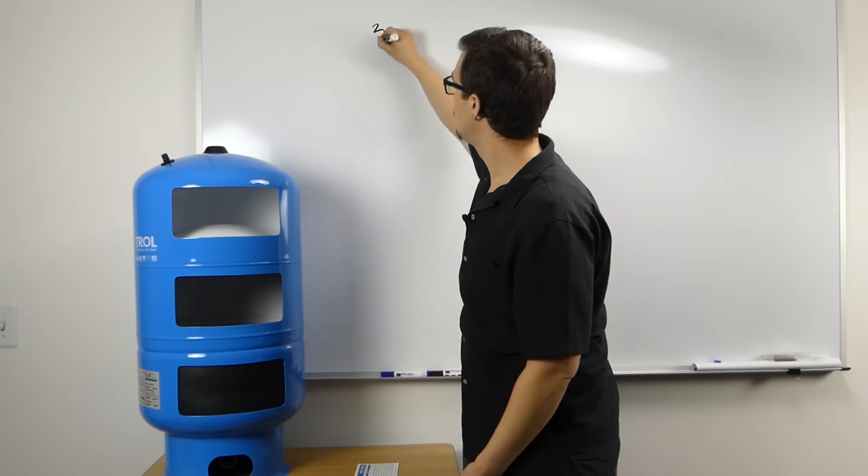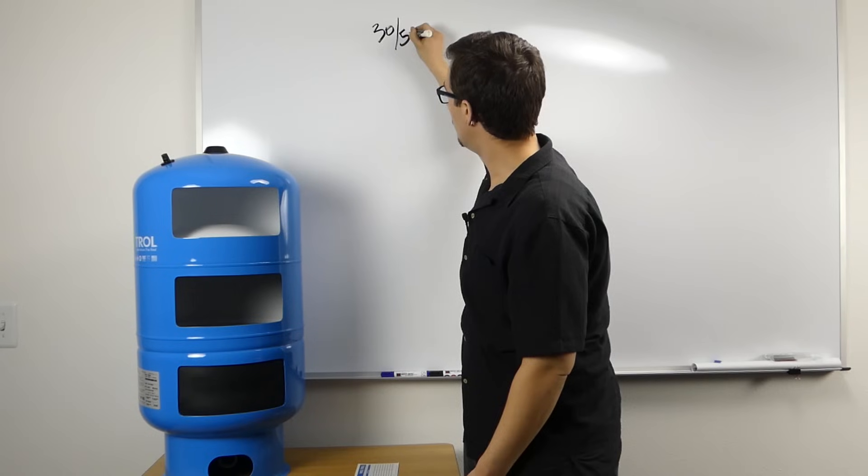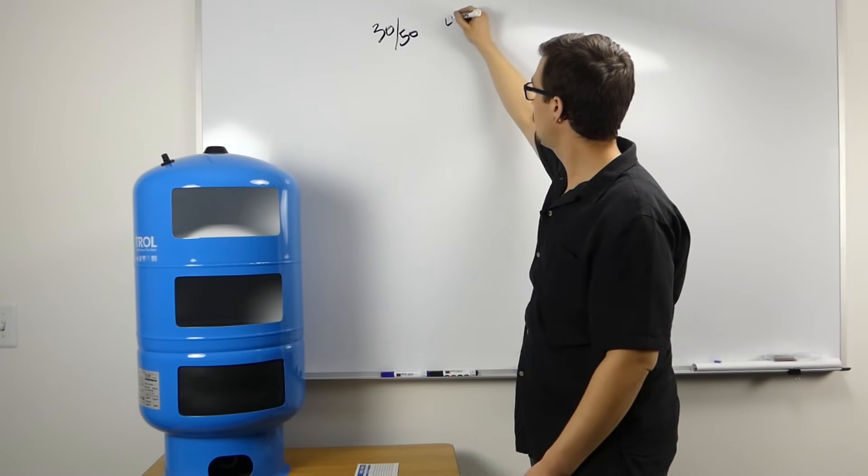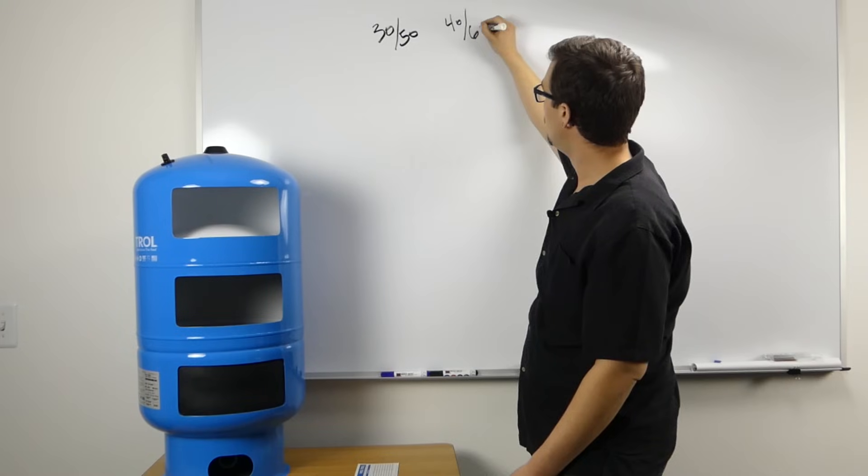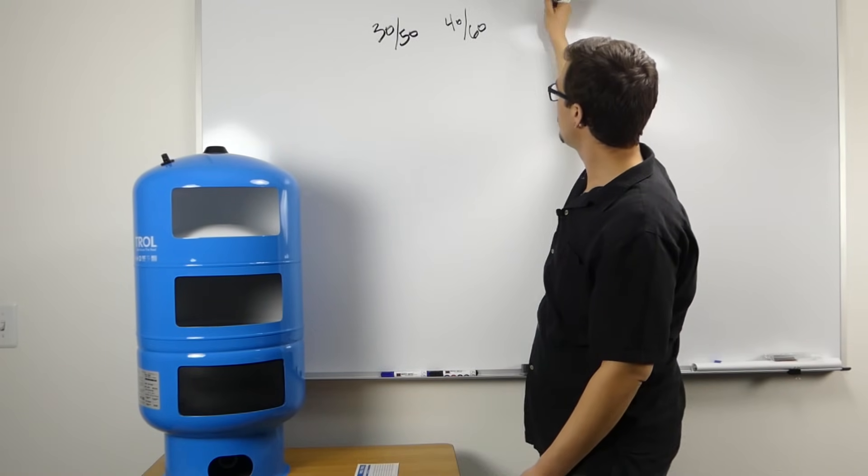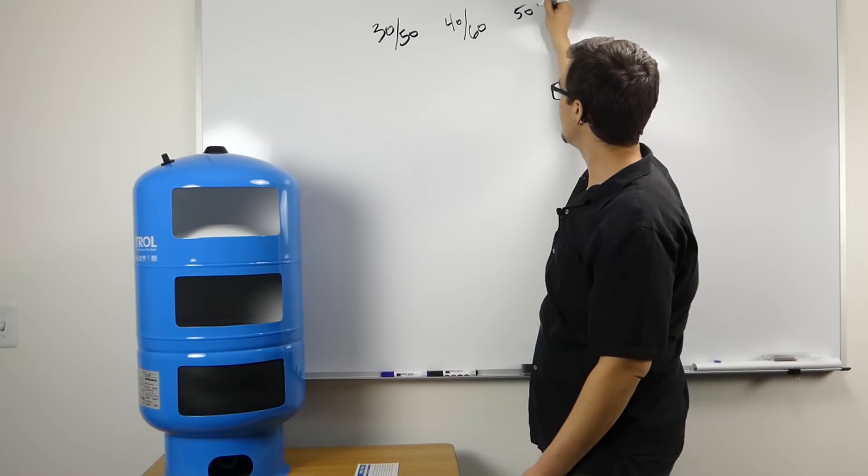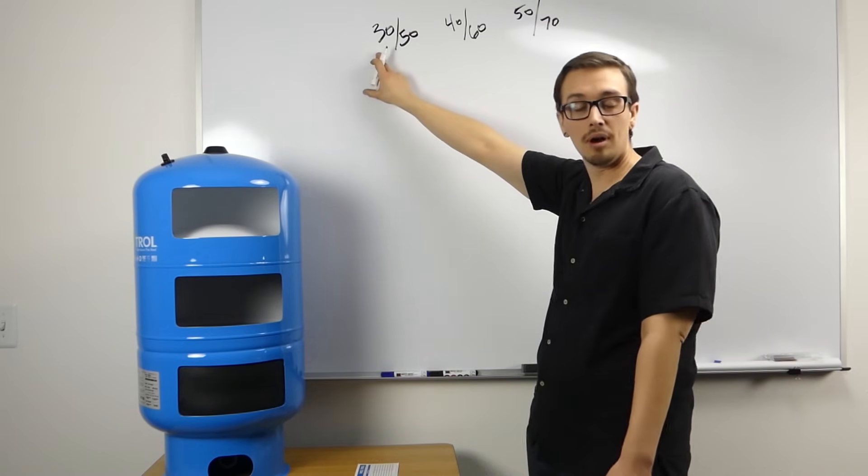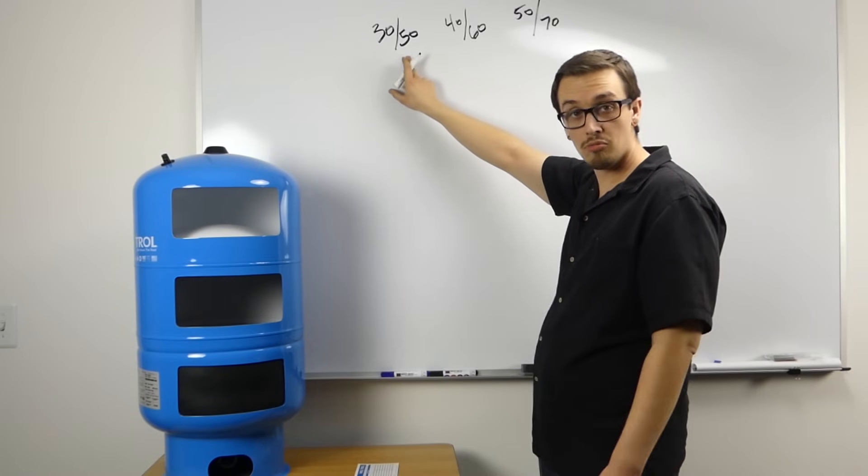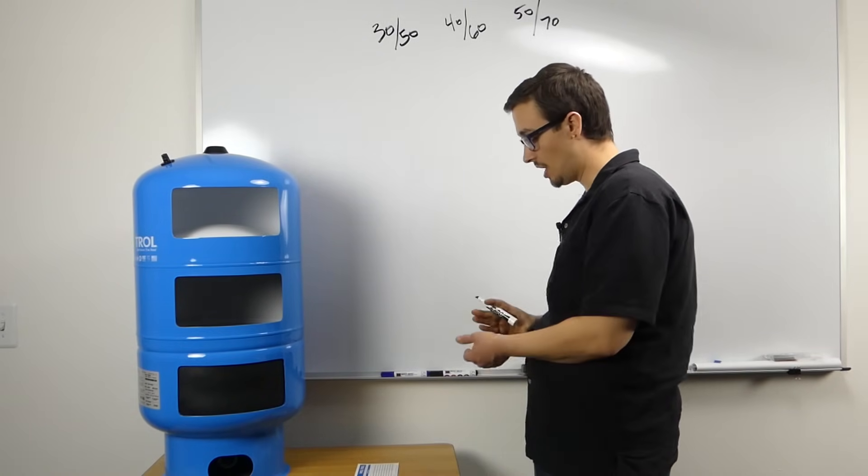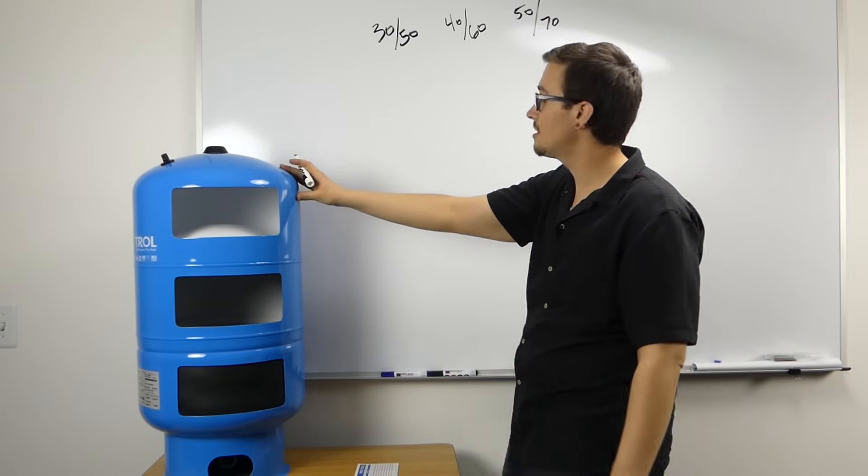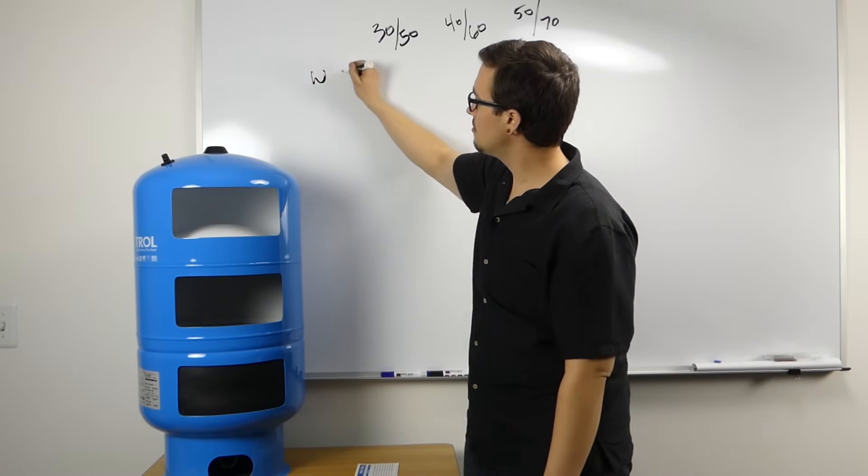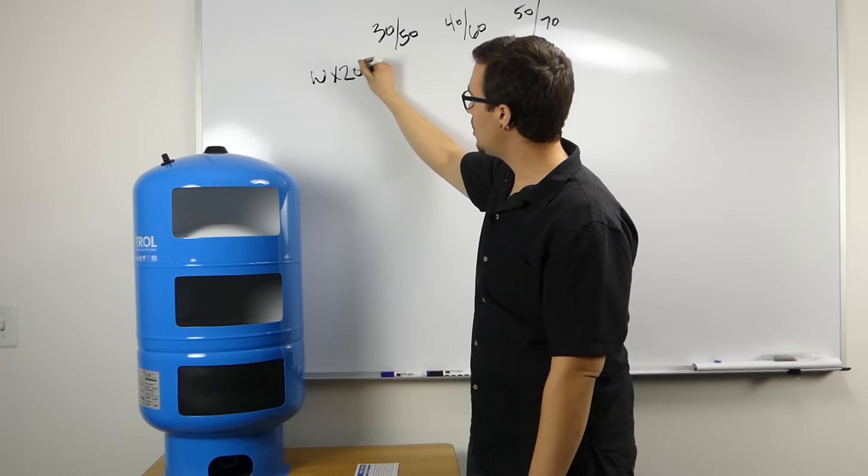The three most common pressure settings on a system are 30/50, 40/60, and 50/70. The low number represents when the pump turns on and the high number represents when the pump turns off. In the example of this tank that we have here, a WX202...